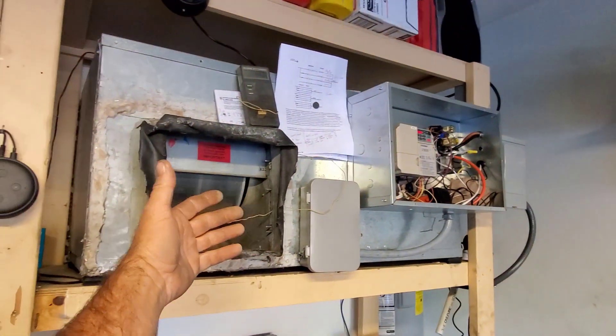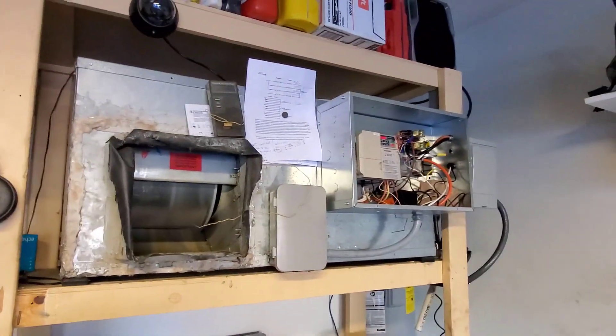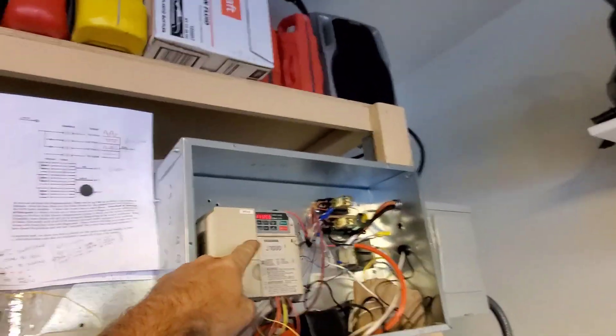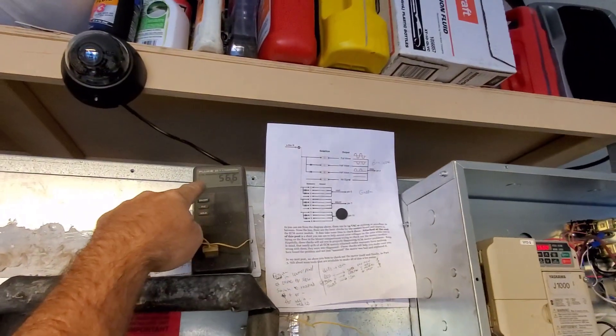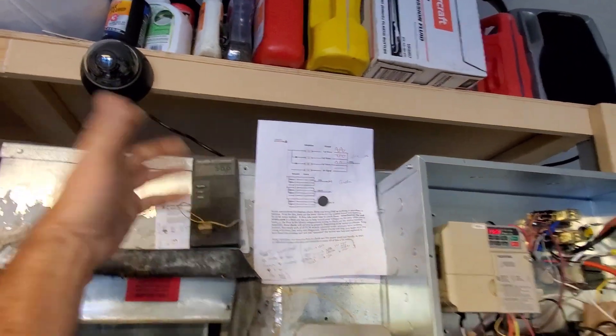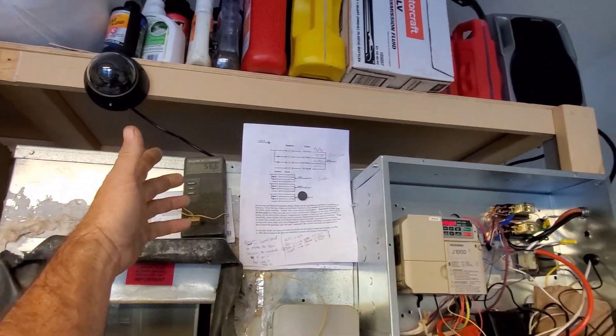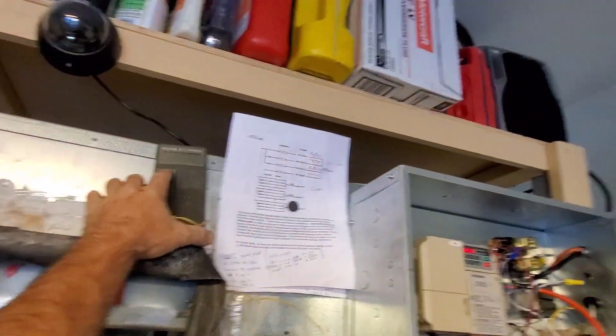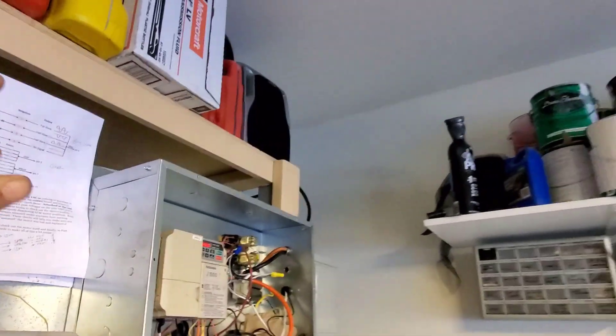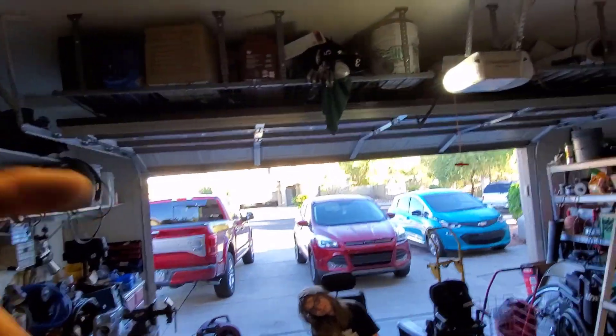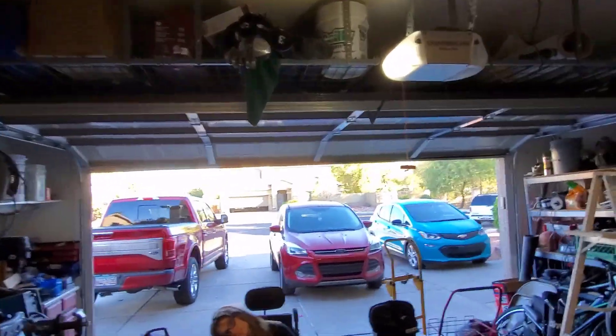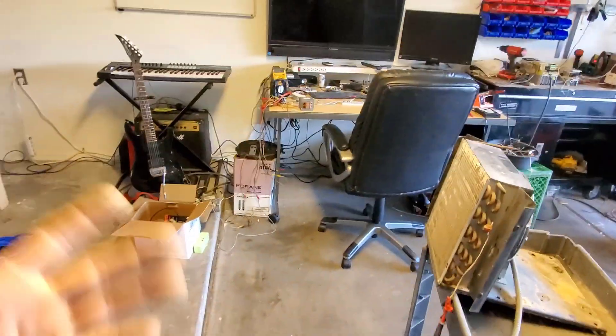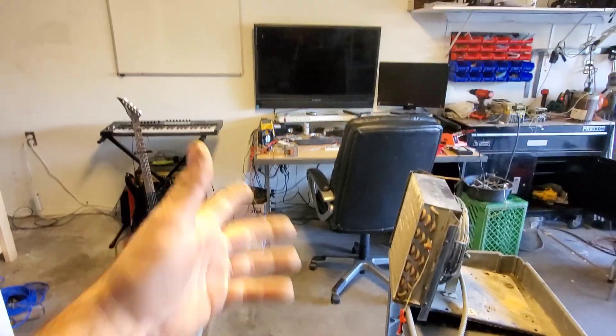But the side effect is it blows cold air into the space. It's down to 35 hertz now, but it's still blowing out 56 degrees. It was blowing 54 a few minutes ago when it was at 40 hertz. Plus it was warmer—or colder—in here before because I had the door shut.